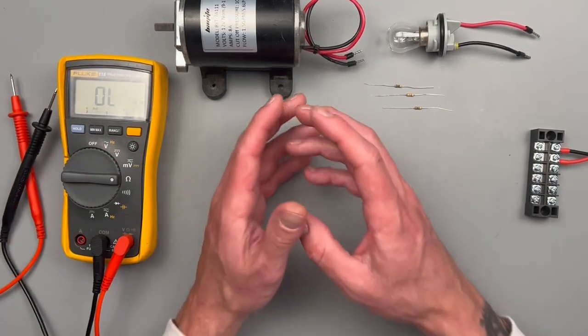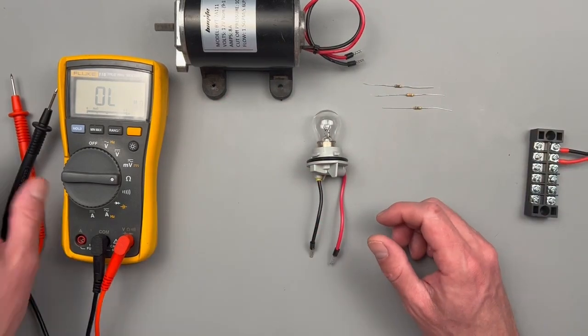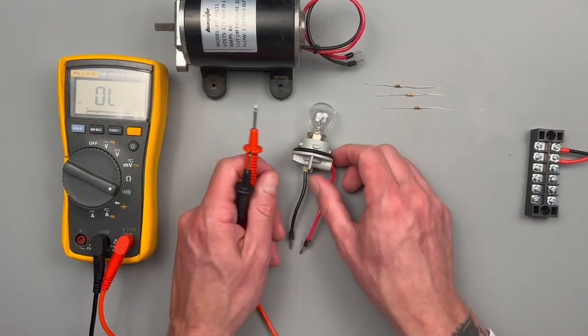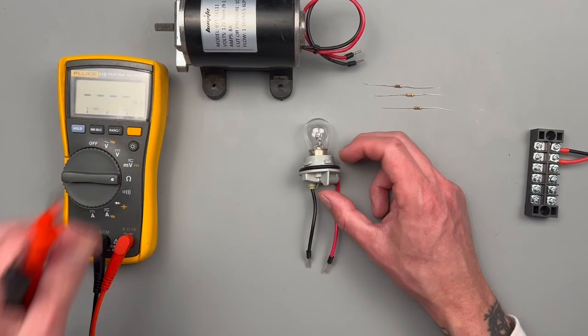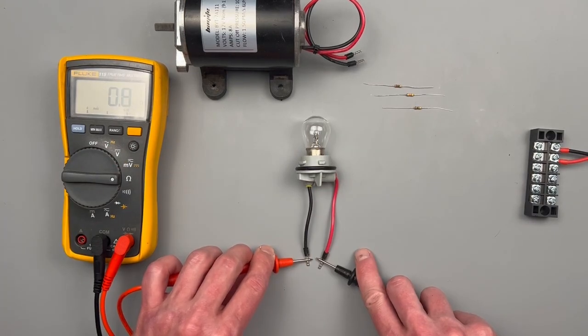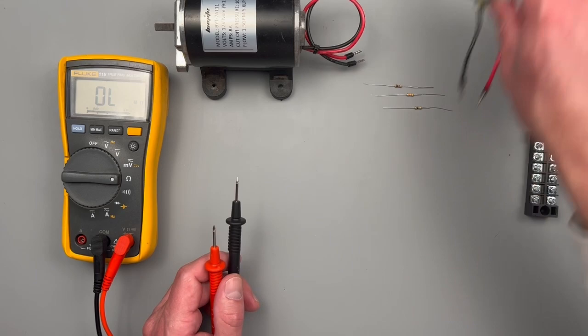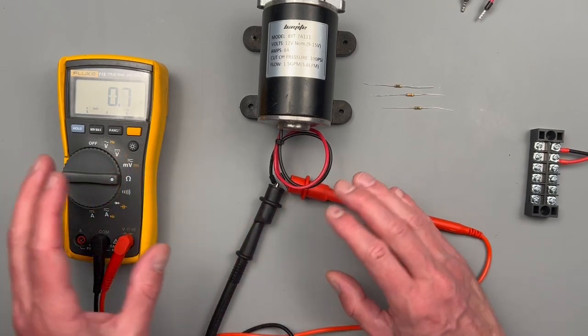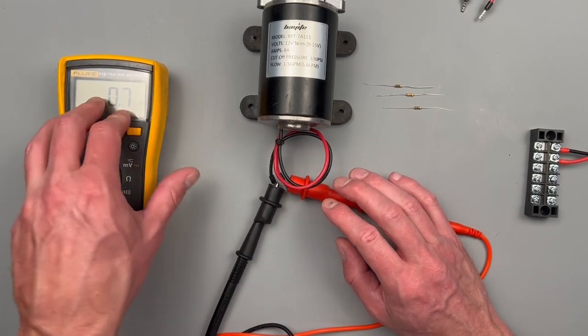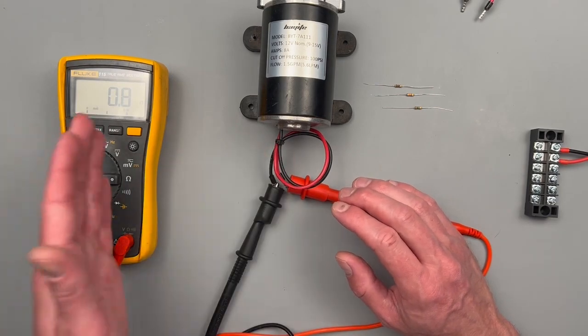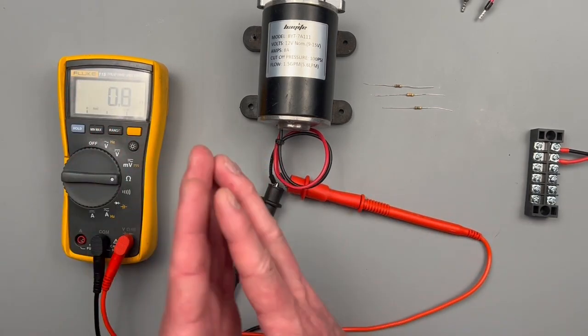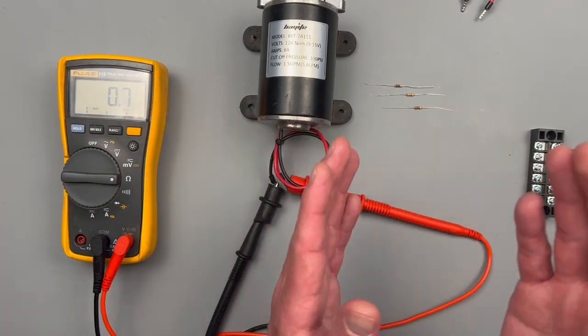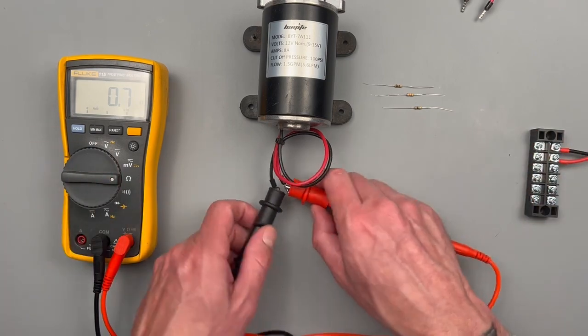Now let's talk about resistance. Resistance is when, say we know we have continuity. Let's take this load. We have continuity. We want to know how much electrical resistance is a part of our load, and that can be handy for troubleshooting. It's about 0.89 ohms. Let's take this motor as another example. It's also showing about 0.8 ohms. So the difference between continuity and resistance testing is resistance testing is going to give us a very precise value, where continuity is probably going to be to the nearest whole number and it's only going to be up to a certain range. When we have our meter to ohms, it'll give us mega ohms, kilo ohms, ohms, and milli ohms, a very large range.